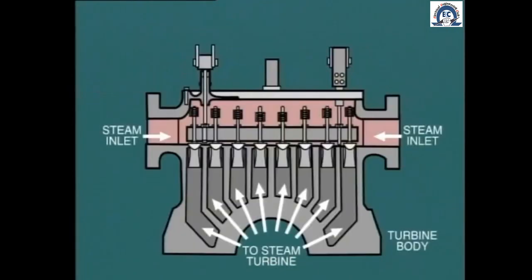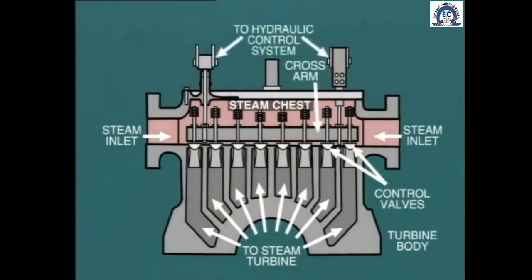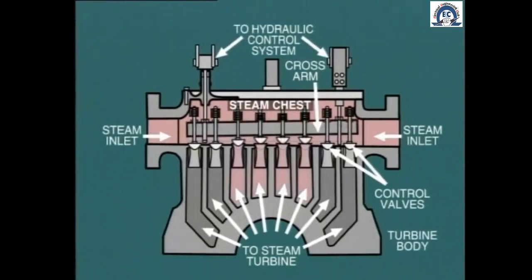In most turbines, multiple control valves are used, as shown here. In this particular arrangement, the steam chest is located above the high-pressure end of the turbine shell. We can see here eight valves, and these are opened in sequence according to the position of the crossarm, which is itself adjusted by the hydraulic control system. These control valves are set in such a manner that only one valve at a time is actually throttling steam, while the others are either fully open or closed, depending on the actual load.